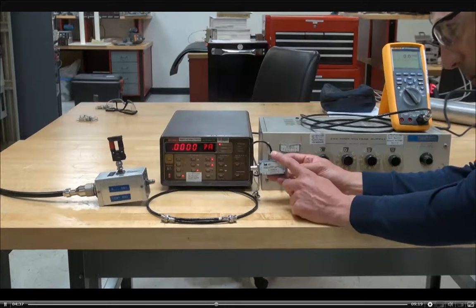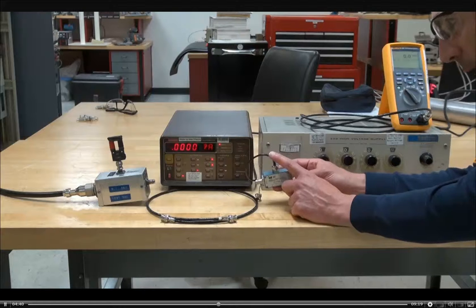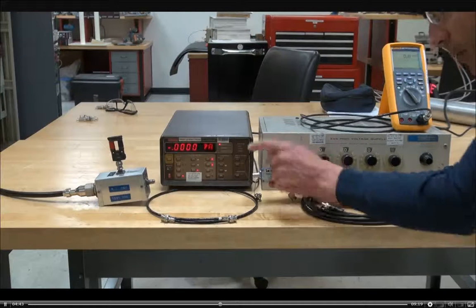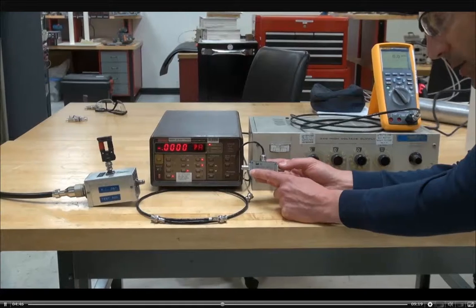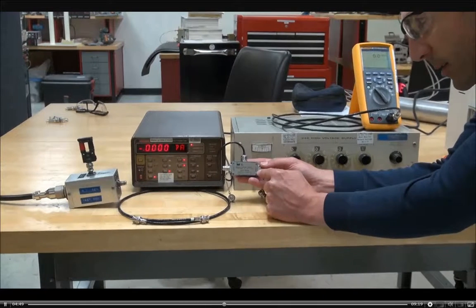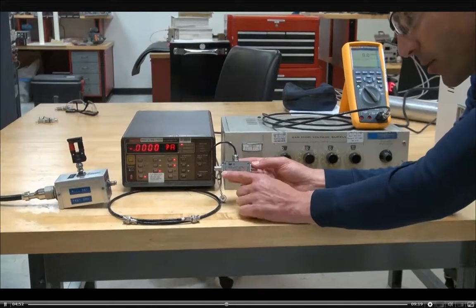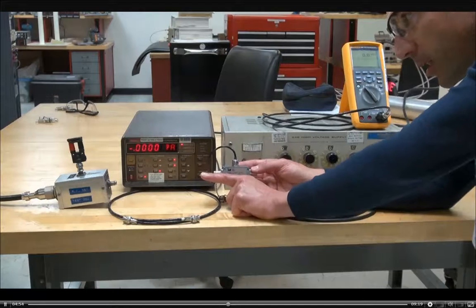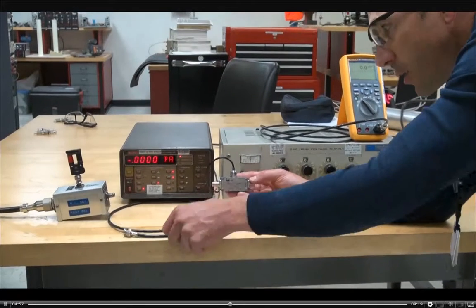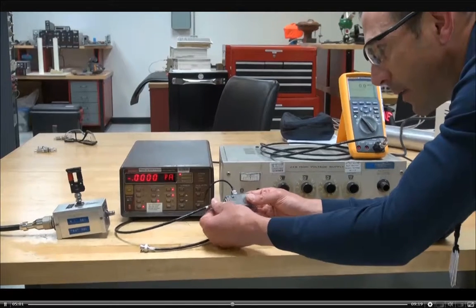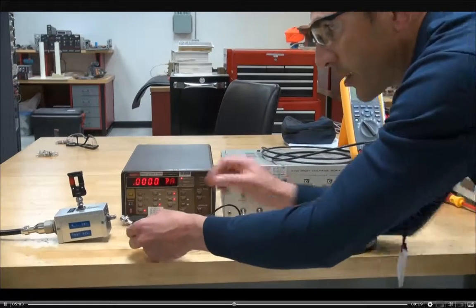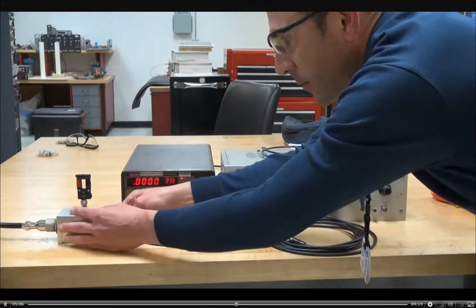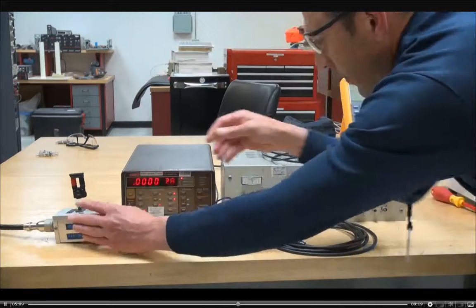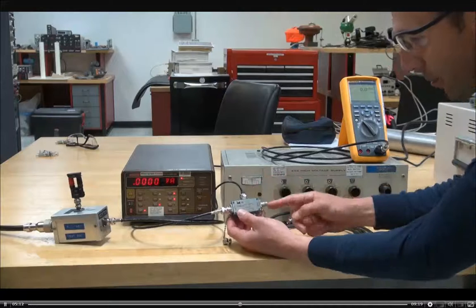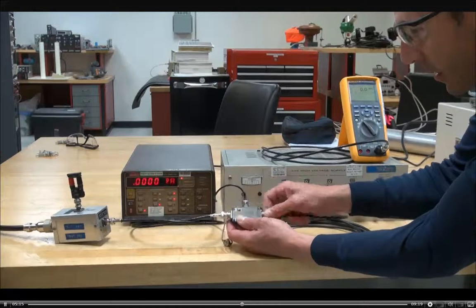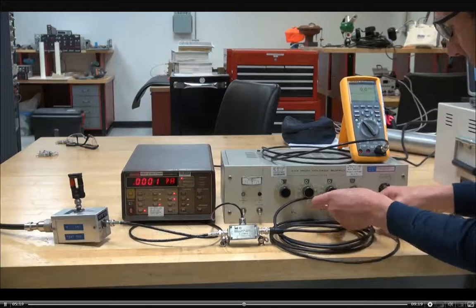The key thing on this, we've already talked about the fact that the top connector with the wire connected to it is going to be what goes to the electrometer. The key thing is, one side is labeled TUT, the other is bias. TUT stands for tube under test. So that connection needs to be going towards the detector. So we're going to connect the BNC cable on that side to the NI detector test box, which is connected to the detector. And then the other side is bias, and that goes to your power supply. So that BNC cable will be connected to your high volts power supply.